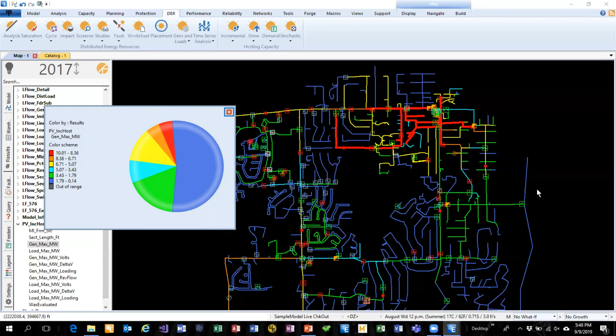So the heat map would be for any section, anywhere. If I go to this section right here, and bring up the pie chart - don't forget about that - this blue section is about half a megawatt or so, and I can click on the section to see the exact value. That means I can put half a megawatt on that section without creating a problem. So it's every single section, it's like the incremental cost. If I were to go in and put in a 1 megawatt generator up here, really I should rerun the incremental hosting on everything, because it's going to impact everything. So incremental is not a feeder level hosting capacity, it's individual sections.